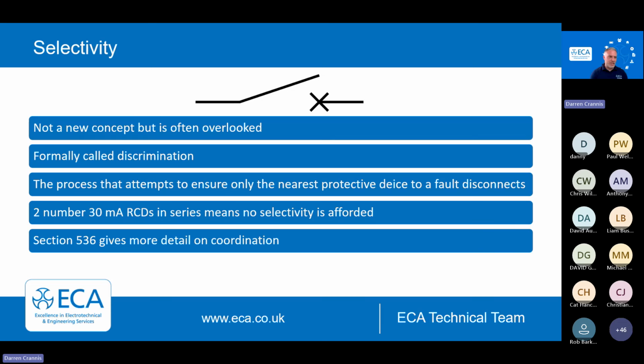We used to call it discrimination up to a few years ago, but it's important that we remember when we design with RCDs. Now, predominantly this might be in TT systems, and it is very achievable. You might see these, especially on EV car parks, for example, that we hit that 3-to-1 ratio: 300 milliamp, 100 milliamp, 30 milliamp. And we can put time delays on the 300s and the 100s. We shouldn't really put two 30 milliamp RCDs in series.